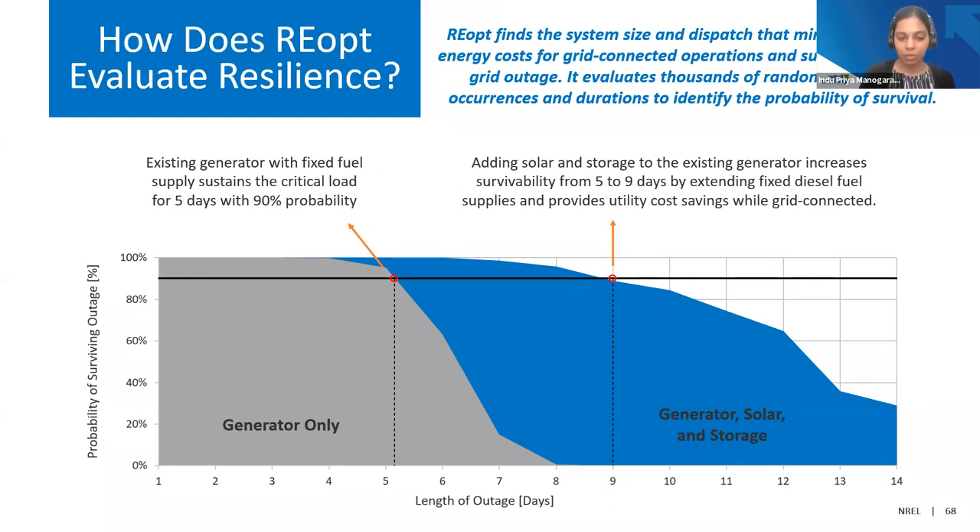When we add a resilience goal to the analysis within REopt, we get an additional set of results in the form of a probability survival curve, which provides an understanding of the probability of surviving a given duration outage. For example, with a generator-only system, the system can sustain a five-day outage at a 90% probability — it can sustain 90% of any five-day outage in a given year, but cannot sustain any nine-day outages. When we add solar and storage, the system can sustain a nine-day outage at a 90% probability — that's where we see the resilience benefit of solar and storage compared to just the generator.